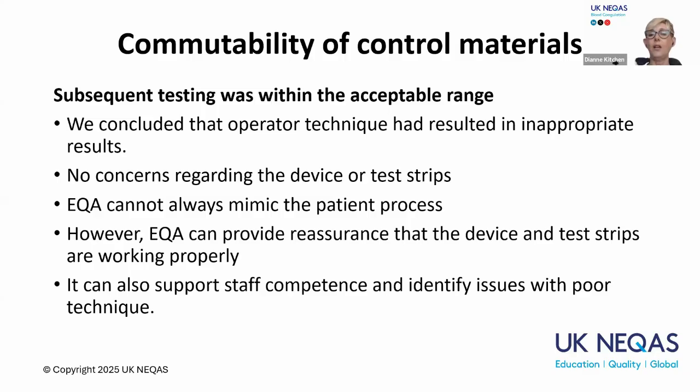So that's a roundup of my commutability issues, the biggest being that we cannot provide native whole blood from a finger stick. We have to find some other way, and we use lyophilized plasma. But I don't know what the rest of the panel think, how big a problem commutability is to you guys.